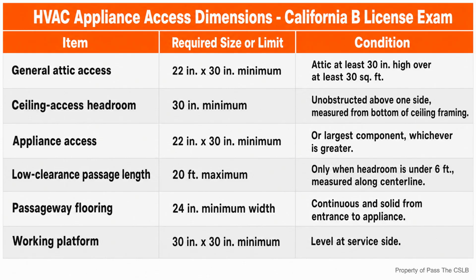The practical effect of the platform is straightforward. It gives the technician a defined, level area to kneel, place tools, open panels, and handle components. I do not need to invent a dramatic explanation for that. The code gives the minimum, and the field condition tells you whether the service side is actually usable. I would verify the platform before the equipment is permanently connected, once gas piping, condensate piping, electrical raceways, duct transitions, seismic restraints, and insulation surround the unit. Moving the platform or rotating the appliance can affect several trades. Early coordination is cheaper than late correction.